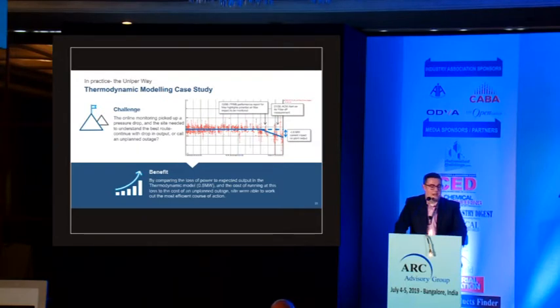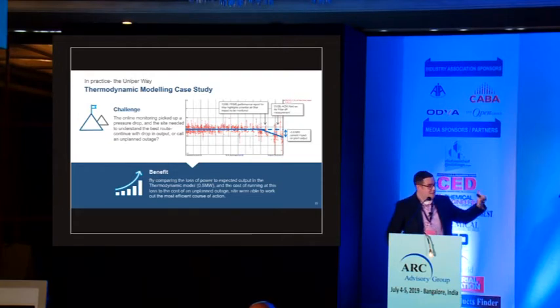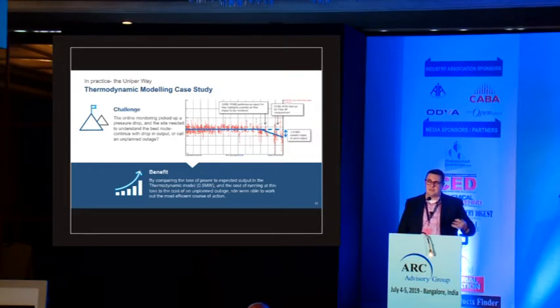Another example: our online monitoring of thermodynamics picked up a pressure drop, and the site needed to understand the best route - whether it was more cost-effective to take the site offline as an unplanned outage and fix the problem, or run to the next planned outage. Using our thermodynamic modeling tool and condition monitoring tools together, we were able to show there was a 0.5 megawatt output impact, and that it was more cost-effective to run to the next outage with that loss than to take it offline and fix the problem there and then. So being able to remain available when the money's there - it was able to demonstrate that.